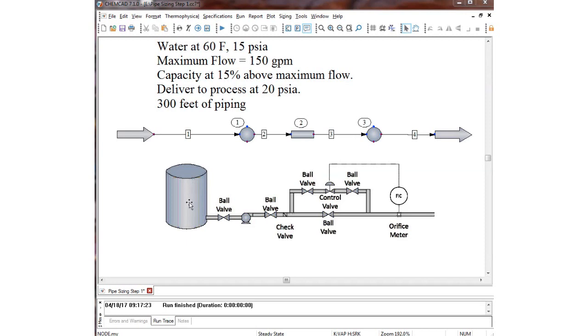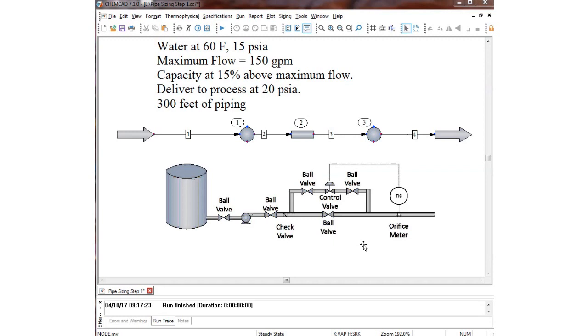The water will flow through a ball valve, a pump, and another ball valve — these isolate the pump for maintenance. We then go through a check valve to prevent backflow into the tank. The control valve loop is teed off, going up through a ball valve, then a control valve, followed by another ball valve, returning to the line where we have an orifice flow meter. We can isolate the control valve with the two ball valves, or open the bypass ball valve to control flow manually.